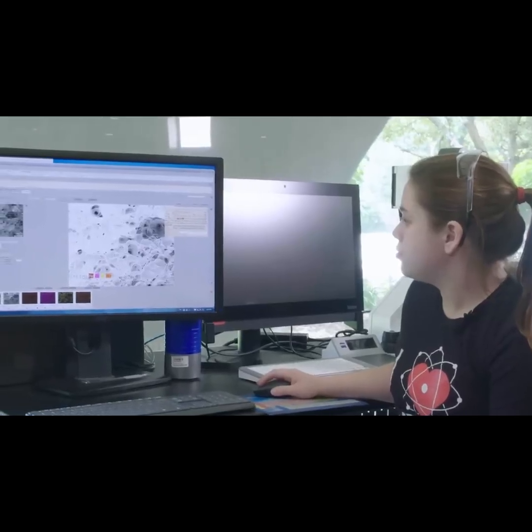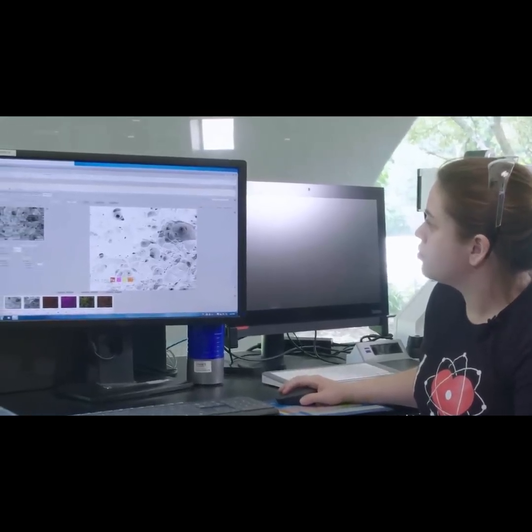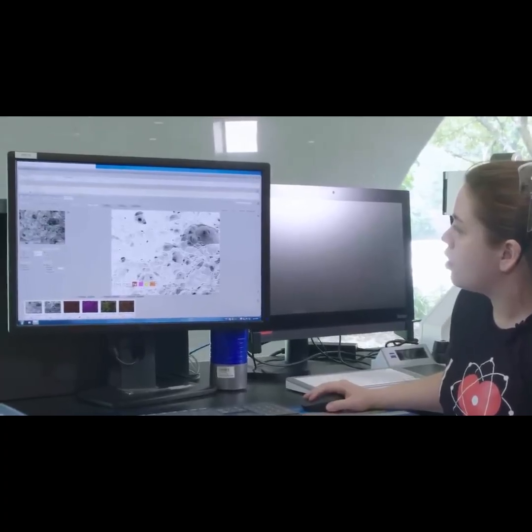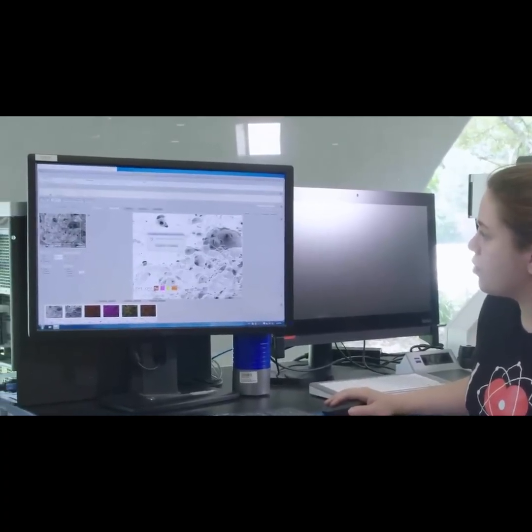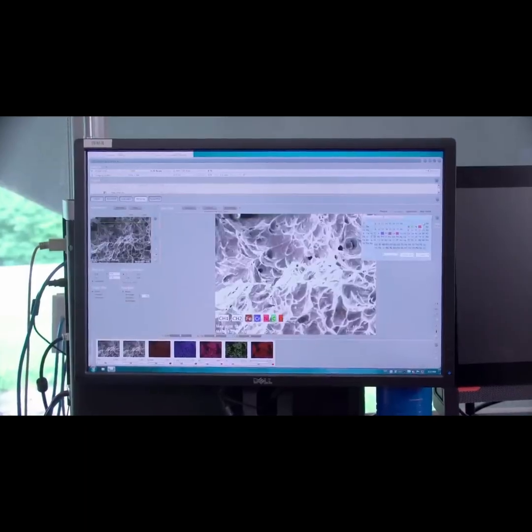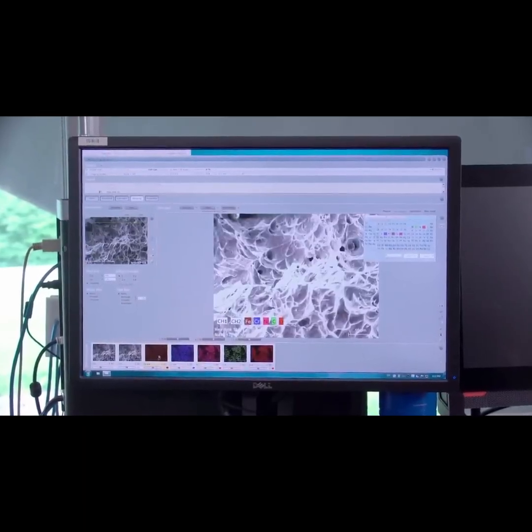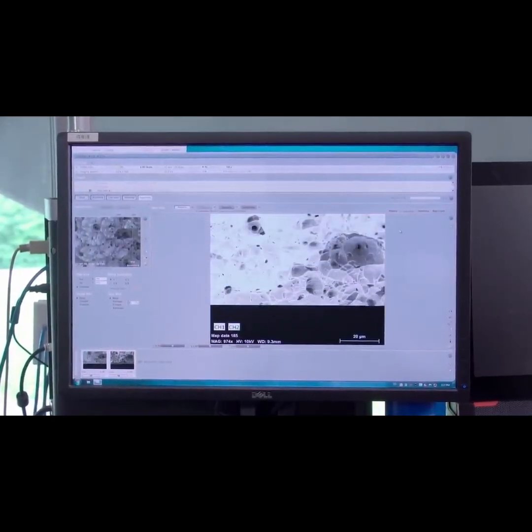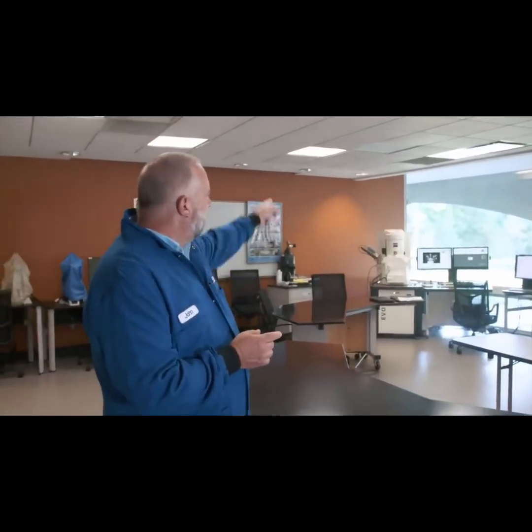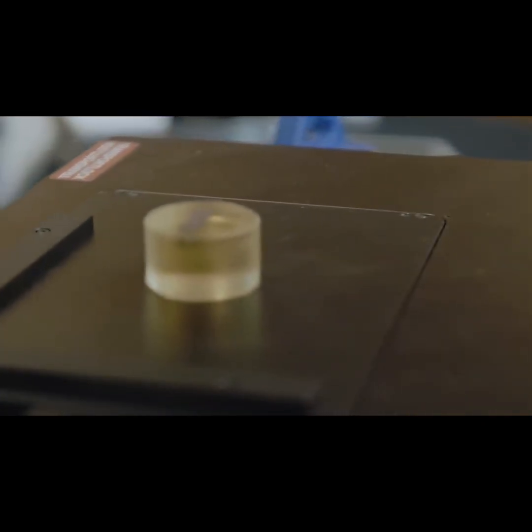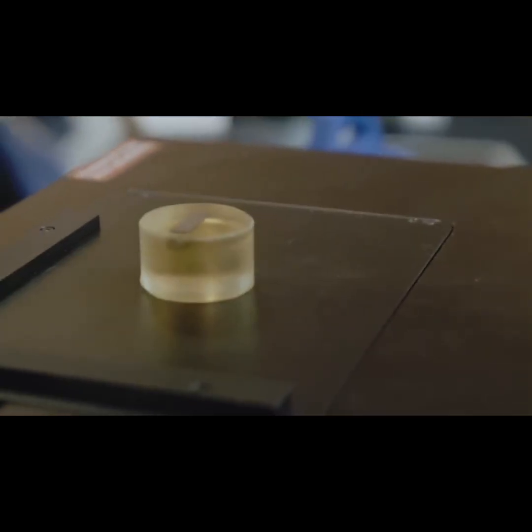On the edge of the electron microscope is an EDS detector. When you're impacting a sample with electrons, X-rays are given off as the electrons get bounced out of their orbitals. Each element has a characteristic signature of those X-rays that are given off due to the interaction of the electron beam with the material. If you can detect those and plot them, then you can do chemical analysis in a scope, and you can have some very nice capability.